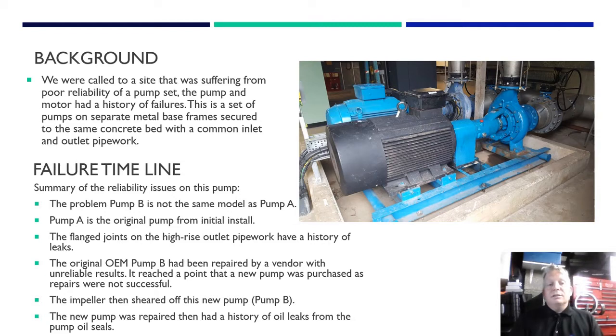With all the case studies in the book we have background, failure timeline, and analysis. Here are the pumps in question - we've got two pump sets. When you go somewhere to do analysis, don't just crack on, take your data, get out and go back to the office. Stand there, chat to the operators, talk about their problems and what pump issues they've had, because nine times out of ten the operators know the history and can be really helpful in guiding you to the correct solution. On this one I had a good chat with them, and you can see we've got a metal frame here with two pumps going into short 90-degree bends into a single header.